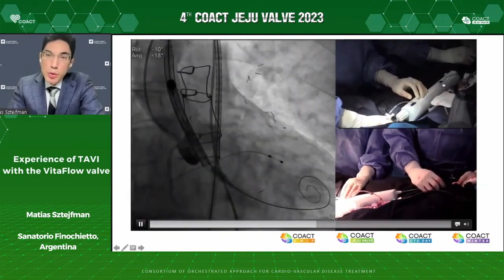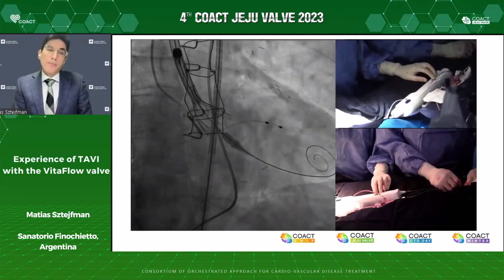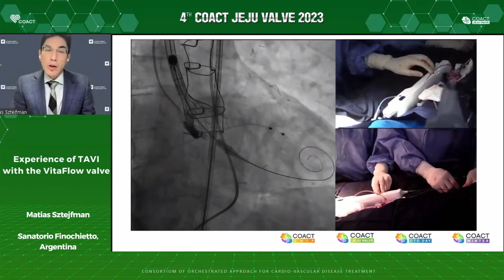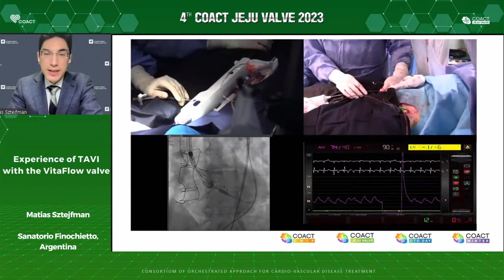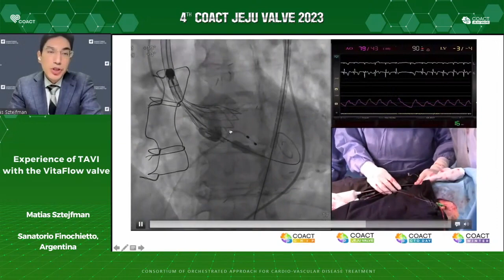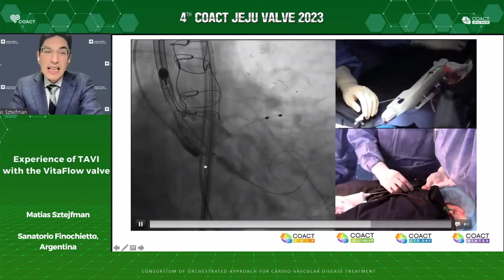We start to push the blue button if we are happy with the position, to start the deployment of the valve. The delivery system comes with one black dot that marks the initial part of the valve, the THV. So look here, the second operator is pressing the blue button and the valve is flowing one-to-one. When we are happy, we push the button continually using wire pacing or rapid pacing, and this is a very easy deployment, okay? And also it's very stable. We use, I repeat, always cusp overlap and rapid pacing during the second part of the release. We are checking here the position of the valve in case we have to recapture, but it looks very nice in cusp overlap and also in LAO projection.